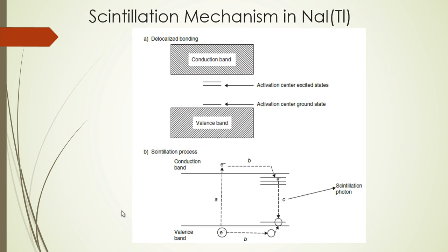When the sodium iodide crystal is not exposed to any radiation, all electrons stay in the valence band and there is no electron in the conduction band. However, when radiation is present — for example a gamma ray photon — it imparts its energy to one of the electrons of the crystal. This electron gains a lot of energy and moves through the crystal, causing ionizations and excitations as it goes.